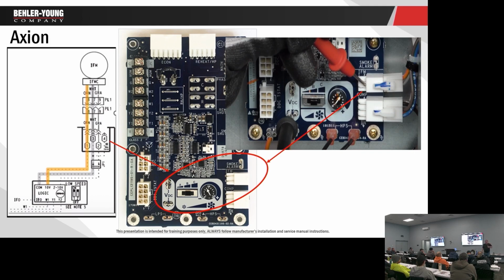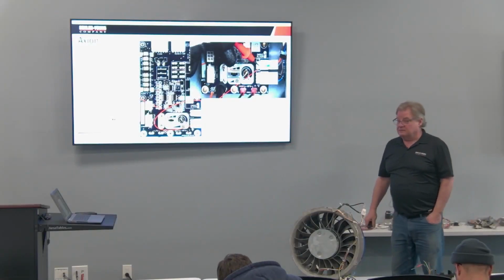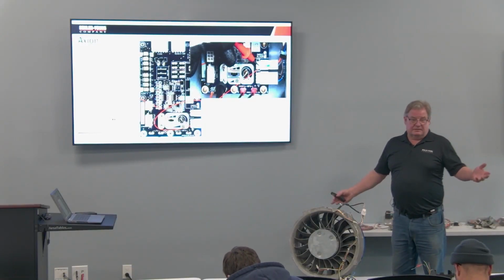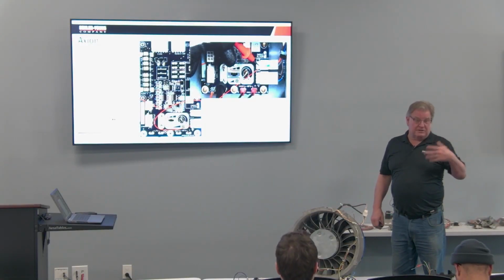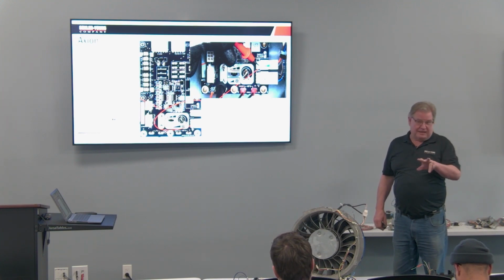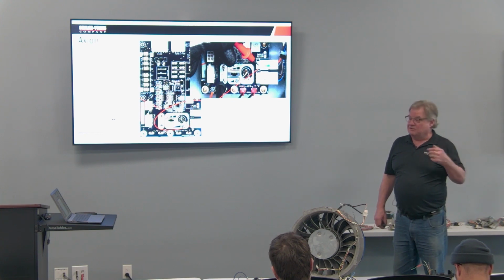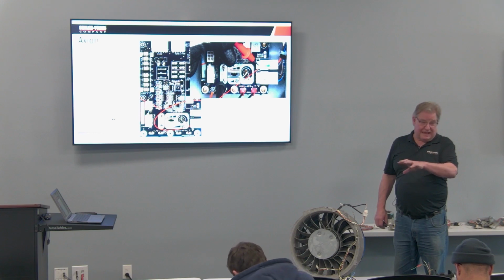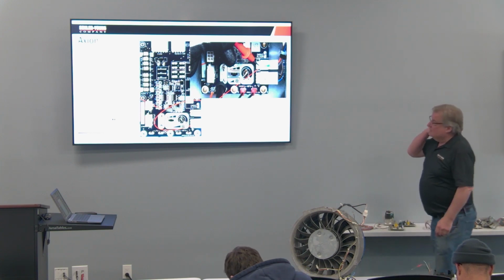Powered up, I should have 10 volts on orange all the time. On a call for blower, whatever that dial is set at should be going down the gray back to the motor to tell it what to do. If I jump those two, the motor should come on. Make sense? It's really, really simple once you understand how to troubleshoot the things. Like I said, if you don't have 10 volts DC, or you have the voltage coming back on gray and the motor's not running, cycle it off, 3 minutes, let the internals reset. It's not an overload, it's a safety circuit.